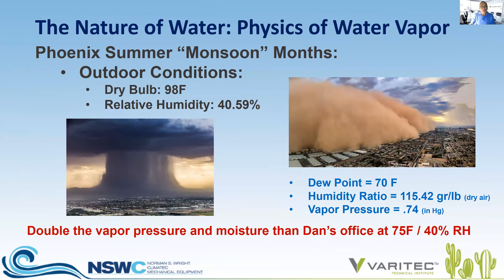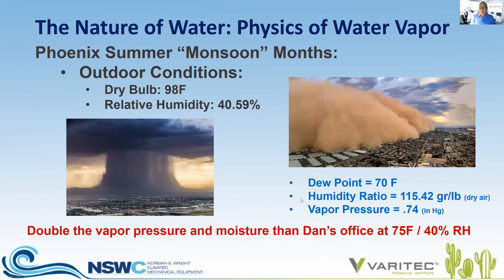In monsoon season, we have a lot of moisture that comes up from the equator and we need to be aware of that in our HVAC designs. A general design condition is 98 degrees Fahrenheit dry bulb. I use a relative humidity during monsoon of 40.59%, which works out to about 78 degrees wet bulb. At that condition, the dew point of the air is 70 degrees — that's when we have moisture forming on cold surfaces, such as a glass of iced tea. The humidity ratio is 115.42 grains per pound, and the vapor pressure is 0.74 — double the vapor pressure and moisture content of my office.